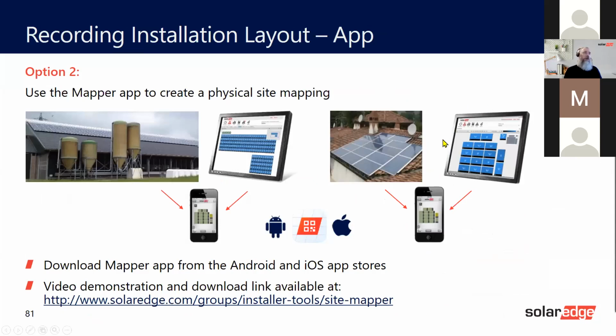What we recommend is that you do it in Designer: create the site in Designer, export the site into the monitoring platform. Once you've exported it, you put that address into your mapping app, and as you're scanning the optimizers, it will automatically update onto the physical layout.